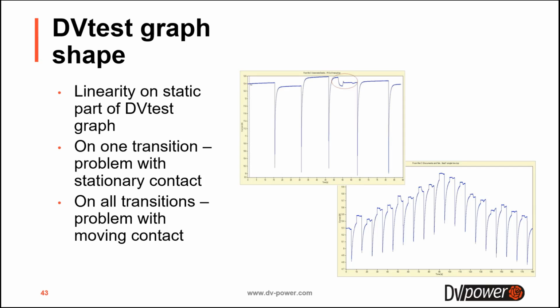So if only one transition is problematic, then most probably the problem is related to the stationary contact. But if you have a problem in every transition, as shown in this second graph in the right below corner, then probably the problem is the moving part of the OLTC, because the chances are low that every stationary contact has the same problem.